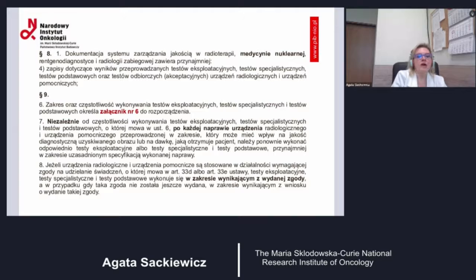We need to remember that after each repair of the device that can in any way impact the diagnostic assessment of the specific study or image, and those administered to the patient, a performance test should be repeated, or even some specialized test, specific tests should be performed to justify the specific change. When we are talking about the radiation equipment, actually we need to have a consent to use them, and the exams can be performed in accordance with this consent.